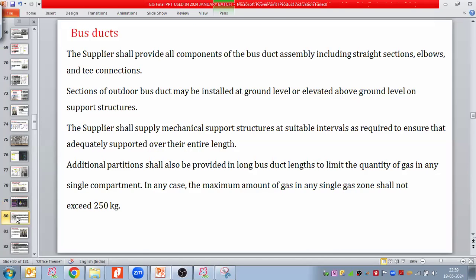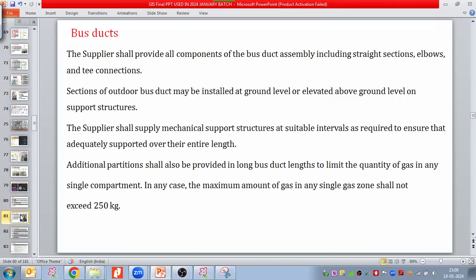Am I clear? So the supplier shall provide all components of the bus duct assembly, including straight sections, elbows, and T connections. Sections of outdoor bus duct may be installed at ground level or elevated above ground level on a support structure. The supplier shall supply mechanical support structures at suitable intervals as required to ensure that the duct is adequately supported over its entire length. Additional partitions shall also be provided in long bus ducts to limit the quantity of gas in any single compartment; the maximum amount of gas in any single gas zone shall not exceed 250 kilograms. This is how much gas we generally fill.